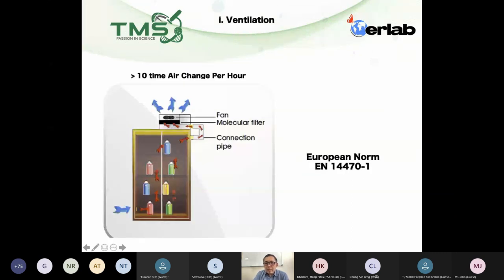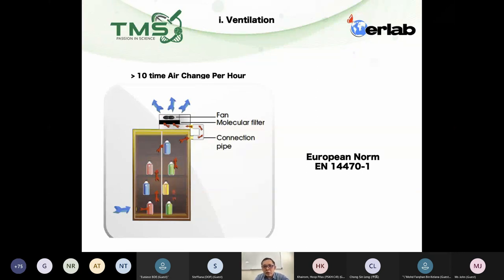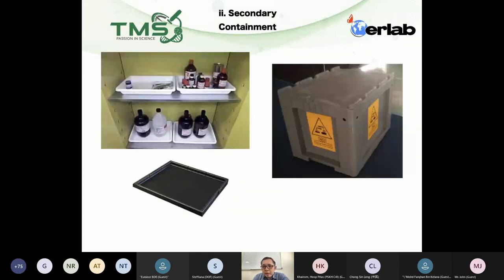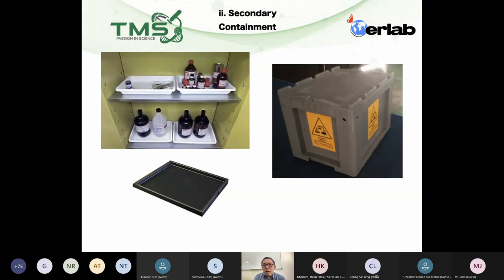There are a few things to consider when storing chemicals in a cabinet in your chemical room. First, ventilation: European Norm EN 14470-1 requires at least 10 air changes per hour, which you can achieve with a filtration box or a ducted system. Second, secondary containment: even for compatible chemicals of different groups, you must segregate them further using a tray, spillage tray, or PP box — PP boxes are best for strong acids to reduce evaporation.